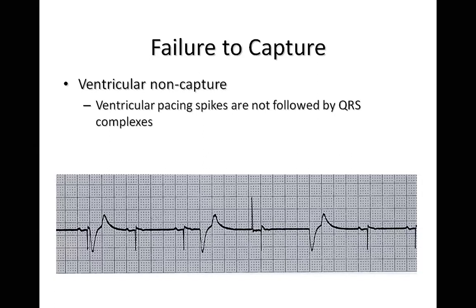Let's say we use 0.5 millivolts to generate QRS, that's the threshold of the patient, the minimum voltage. It does not mean that 100% of the time it's only the 0.5 that will generate QRS. The myocardium can change in nature, and you'll be needing higher energy to generate the QRS. So maybe it can change to 0.7. Later, the tissue can change to 0.8.